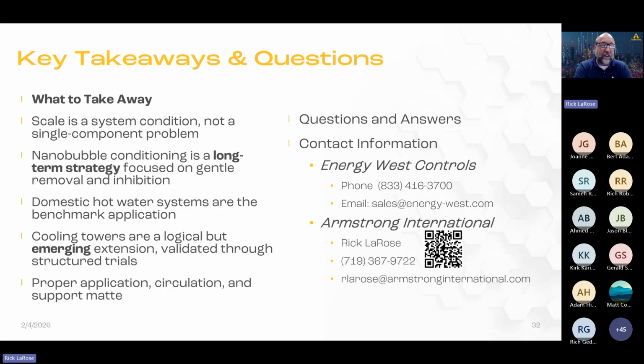The chemistry of condensate is not conducive to nanobubbles. Also, as you approach the flash point into steam, nanobubbles are history, they don't work. So we don't recommend nanobubbles for condensate, boiler feed waters, hot water boilers, steam boilers, closed loop boiler water systems, or closed loop chill water systems. I wish that were the silver bullet I could give you, because I understand that problem, but we don't have the proper conditions. So they're only recommended for domestic hot water, cold water, and cooling towers.